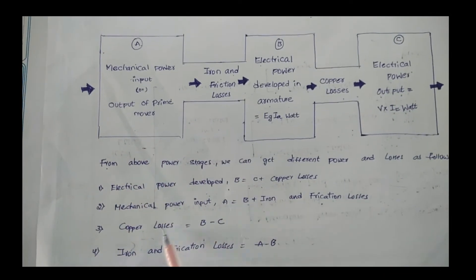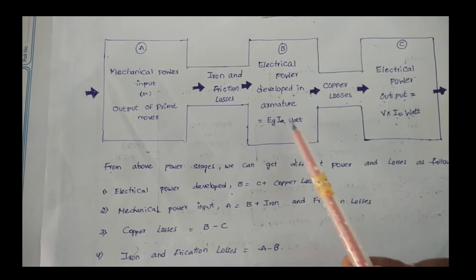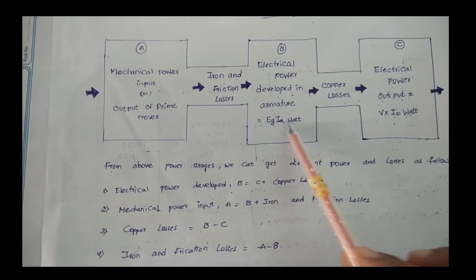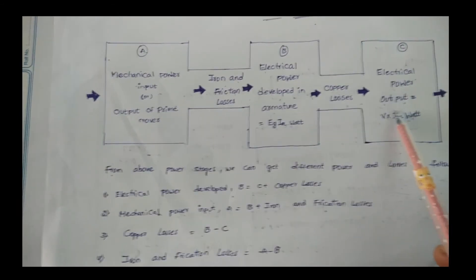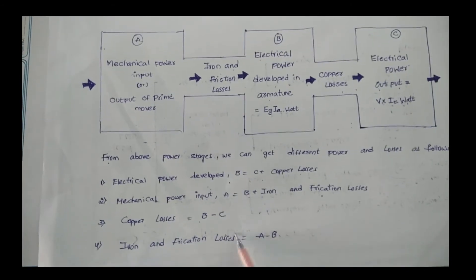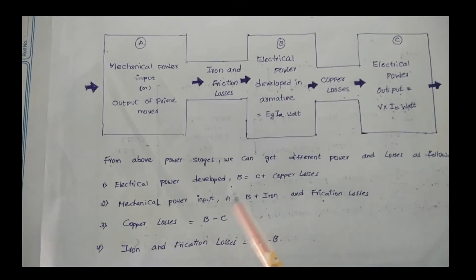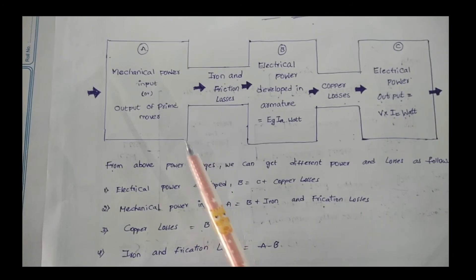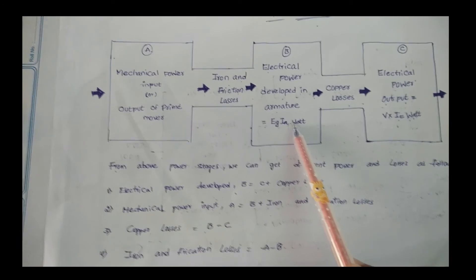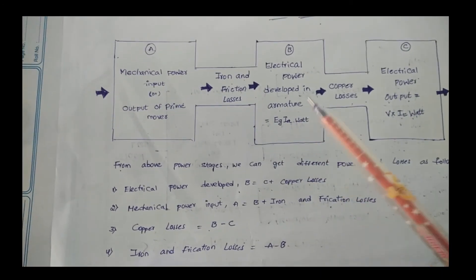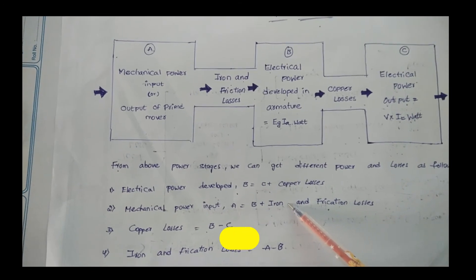The copper losses can be found by subtracting the electrical power output from the electrical power developed in the armature. Similarly, the iron and friction losses equal the mechanical power input minus the electrical power developed in the armature. I have given a brief overview of the losses in this video.